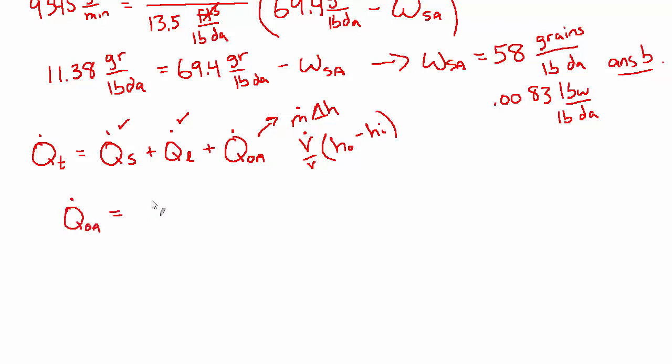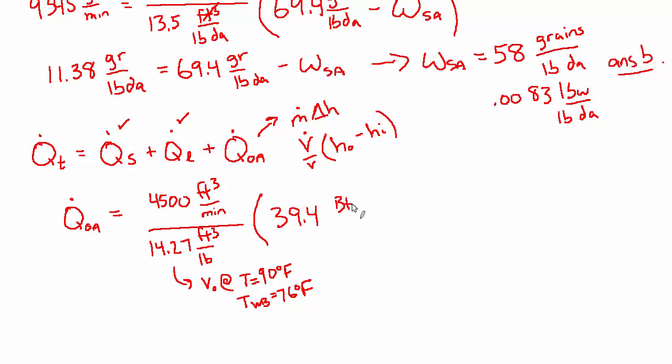So let's calculate this bit. Q dot outside air equals 4500 CFM, I'll write it as cubic feet per minute so we can see the units cancel, divided by the specific volume at the outside air condition, which is 14.27 cubic feet per pound. And I'm pulling that from the psychrometric chart or from a psychrometric calculator, whichever is easier for you. The specific volume of the outside at T equals 90 degrees and a wet bulb equals 76 degrees. And that's being multiplied by the difference in enthalpies. 39.4 BTU per pound is the enthalpy outside, again associated with these same conditions here, minus the enthalpy in the room, which is 29.3 BTU per pound. And that's associated with the room conditions.